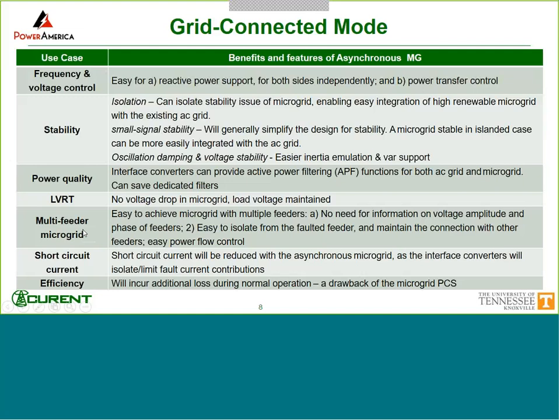Another benefit is that it's easy to connect to a microgrid with multiple feeders. And the short circuit current, this may or may not be a benefit because of these converters, and the short circuit current will be defined by the converters rather than by the loads. Of course, when we add this link in between, it will cause additional loss during normal operation, so that is something we have to take care of.